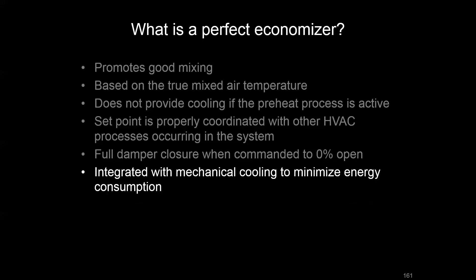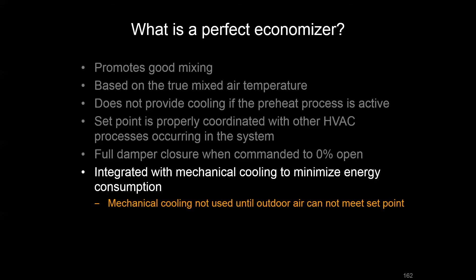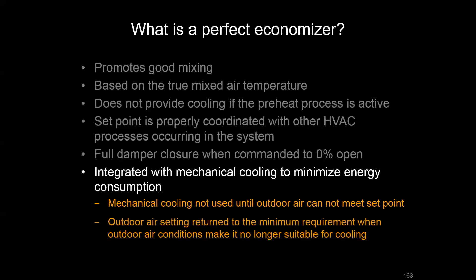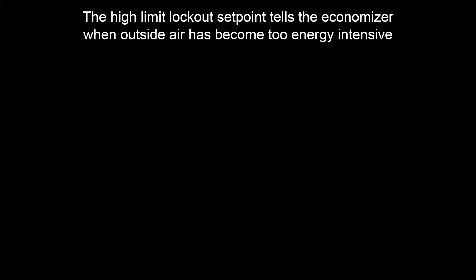Lastly, we want an integrated economizer cycle. When we need mechanical cooling and can no longer achieve our supply air set point with outside air alone, we still want to keep using outside air as long as it's less energy intensive than return air. This means having an economizer lockout or high limit disable that stops using outside air when that outside air has greater energy content than the return air.